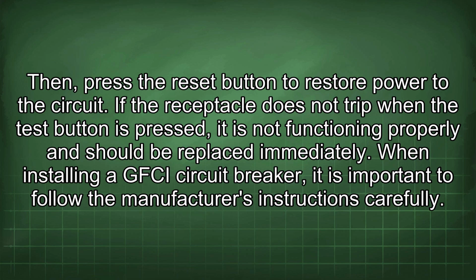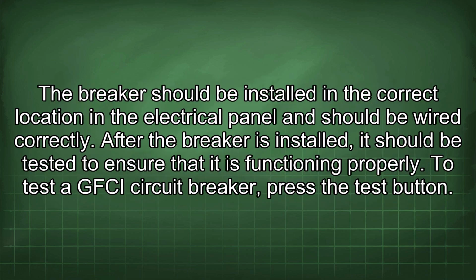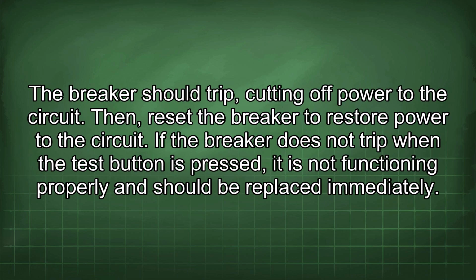replaced immediately. When installing a GFCI circuit breaker, it is important to follow the manufacturer's instructions carefully. The breaker should be installed in the correct location in the electrical panel and should be wired correctly. After the breaker is installed, it should be tested to ensure that it is functioning properly. To test a GFCI circuit breaker, press the test button. The breaker should trip, cutting off power to the circuit. Then reset the breaker to restore power to the circuit.